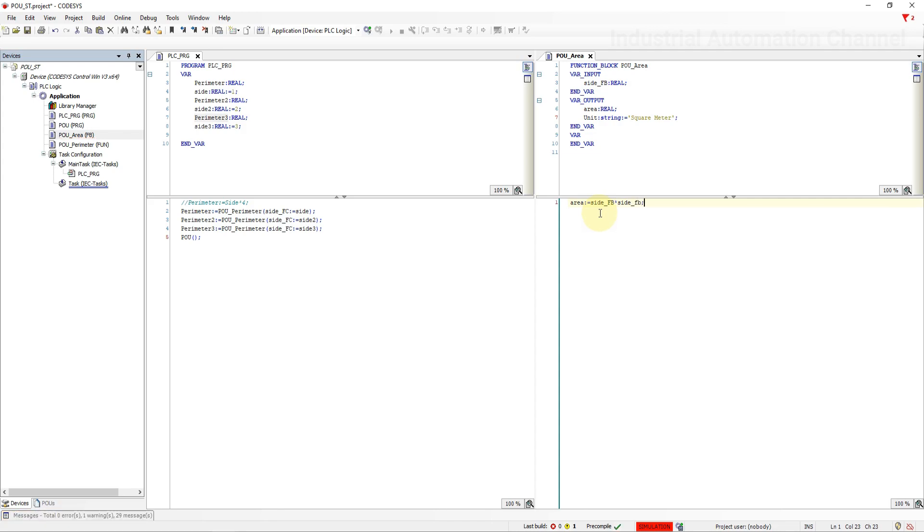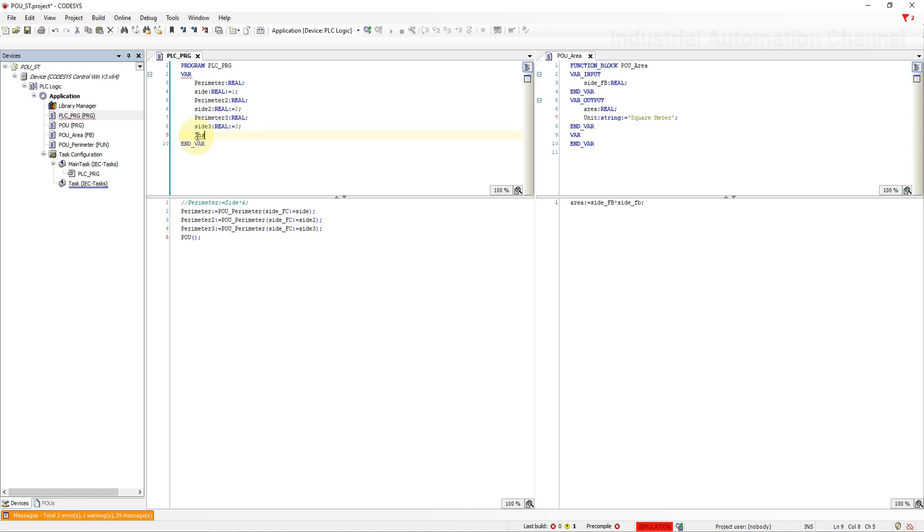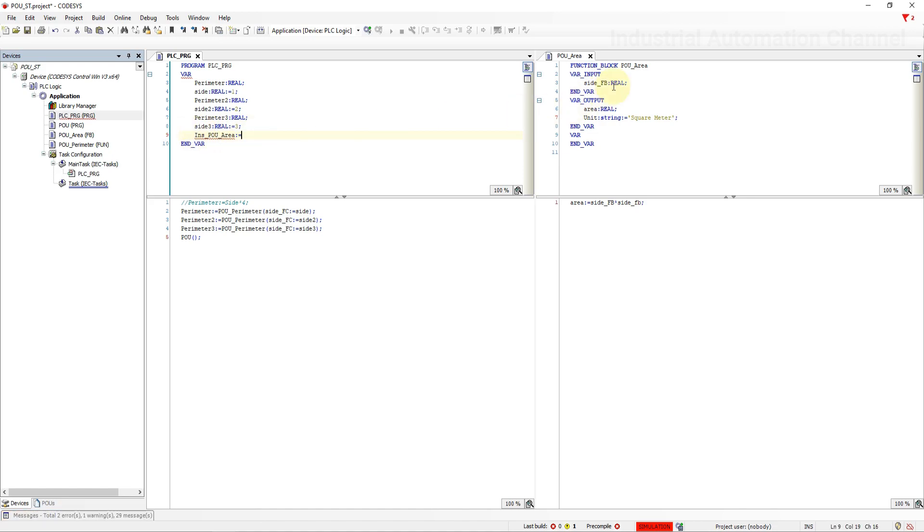As I said function block saves the data for the next cycle using an instance. The call of a function block always takes place via this instance of the function block and Codesys stores the result of a function blocks call inside this data block. So inside the main program we need first to declare an instance for our function block. Write a name with assignment and then the name of your function block.